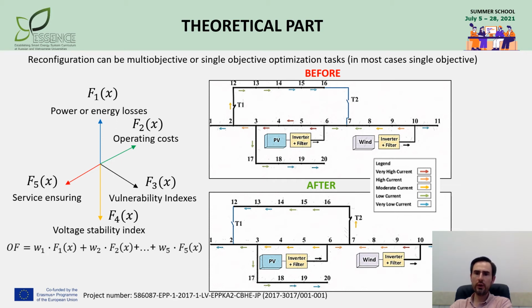But it often contradicts the need to maintain certain voltage profile, which requires additional generation of reactive power and thus increases losses. There is a more complex economical objective which deals with minimization of operating costs. It usually accounts production costs, namely the prices of energy consumed from the main grid and from distributed resources. Sometimes maintenance costs and costs of switching are also counted to consider equipment resources.